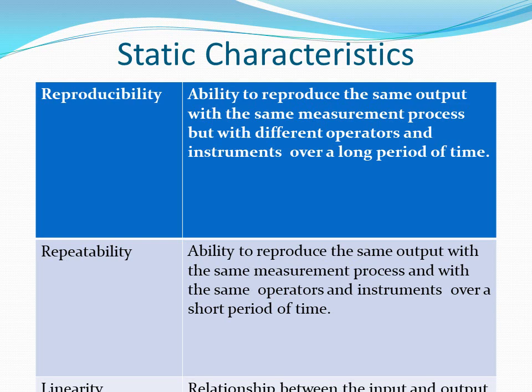Reproducibility is for a longer time, repeatability is for a shorter time. Reproducibility is the ability to reproduce the same output with a different operator and a different instrument. Repeatability is the ability to reproduce the same output with the same operator and the same instrument.